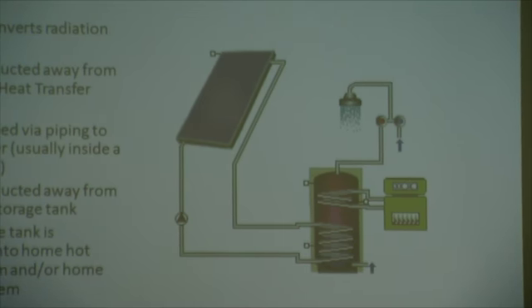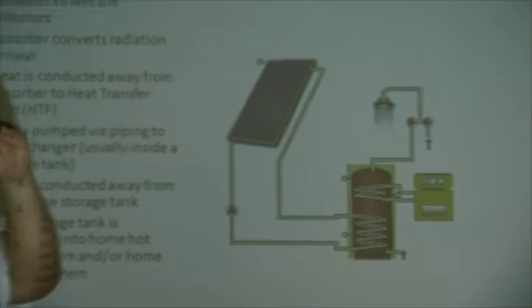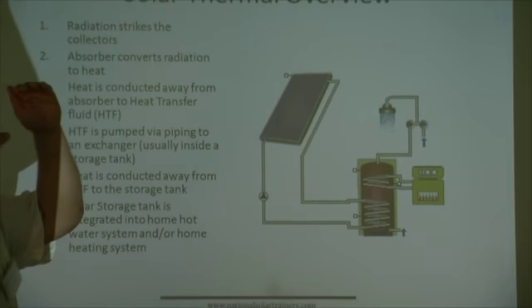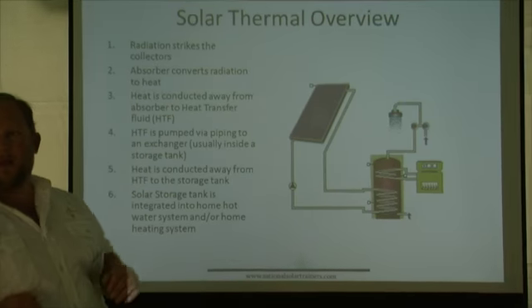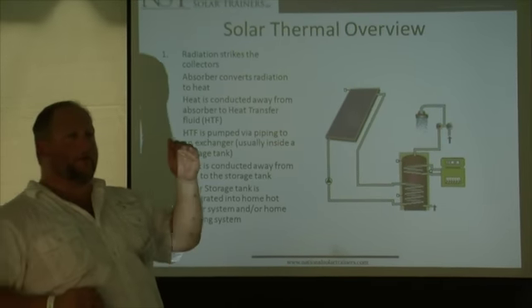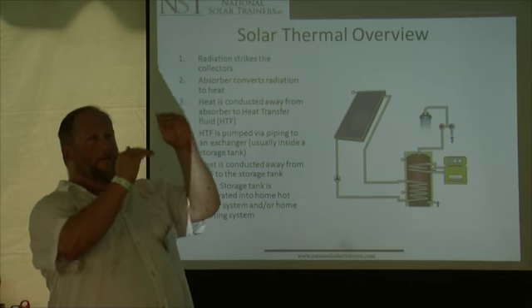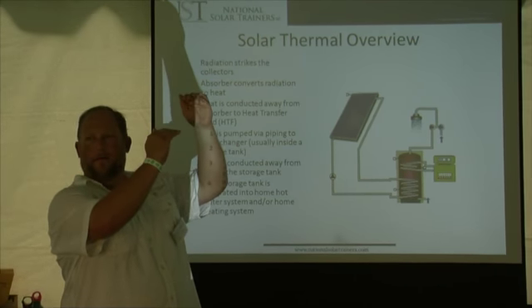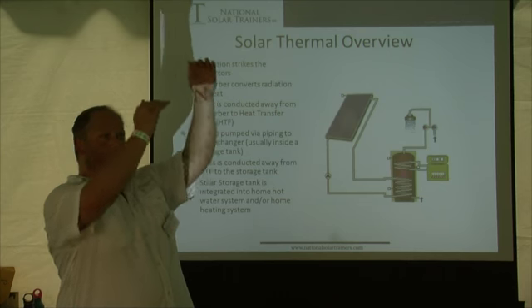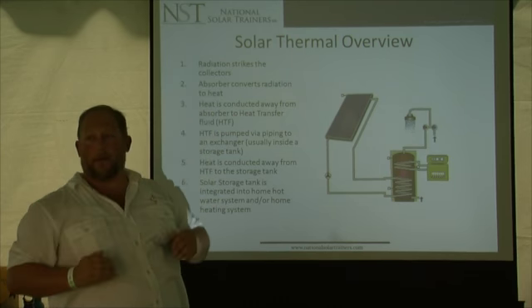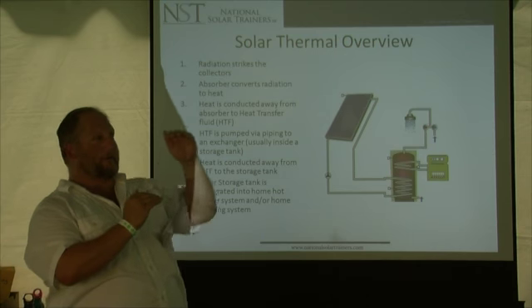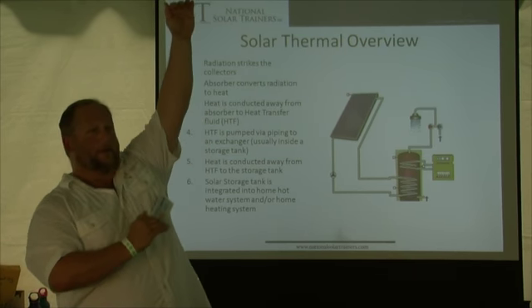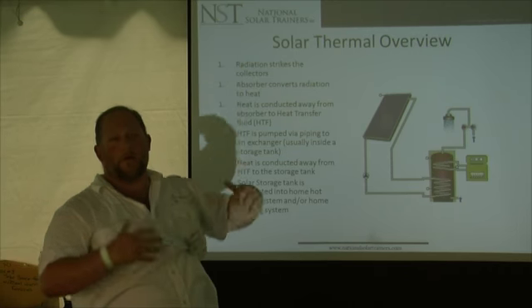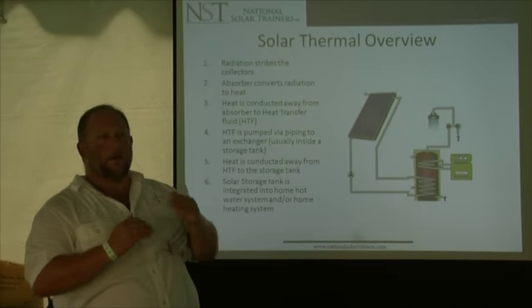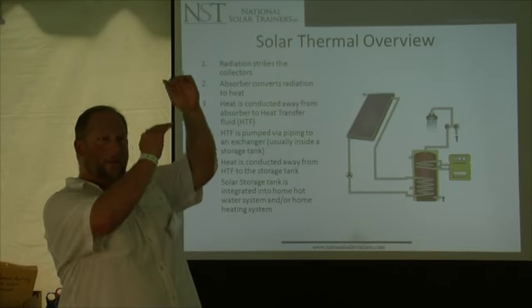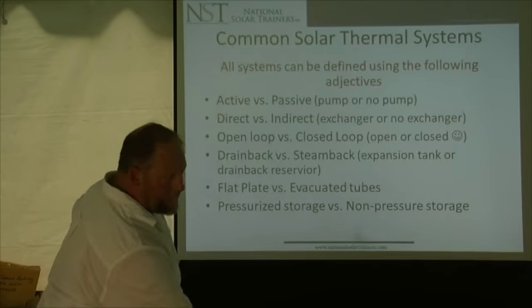Slowly, the collector temperature and the tank temperature climb all day. At 8 in the morning, the collectors are 100 and the tank's 90. Then it's 105/95, 110/100, 115/105 — it keeps going up incrementally. But if the collector temperature climbs while the tank temperature stays down, that tells you there's an issue with heat exchange and flow rate. So you should always see the temperatures climb incrementally.